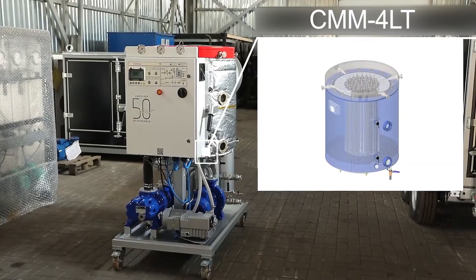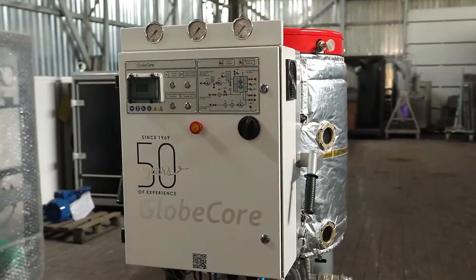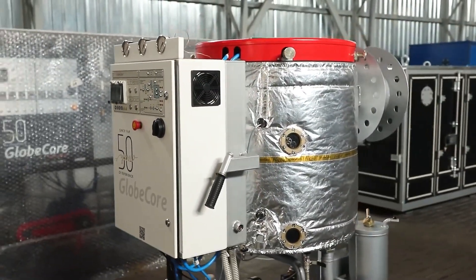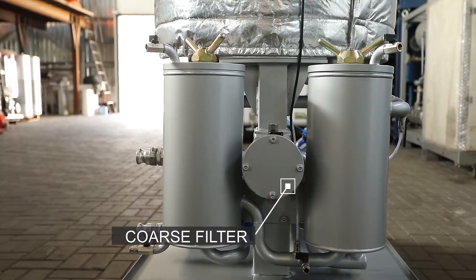The first feature of the CMM-4LT unit design is an innovative system of pumping oil using a vacuum. A pressure much lower than atmospheric is created in the unit's vacuum vessel. The oil enters the unit through the pipeline and through the coarse filter. Due to the pressure difference, an additional pump is not required.